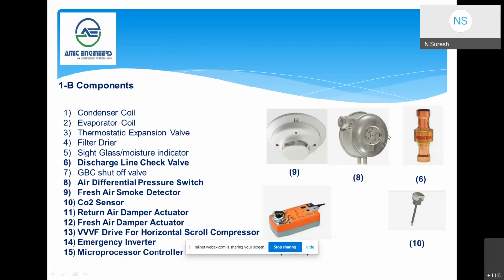So earlier there was no pressure switch, so the filter would get clogged and we would be running the compressor for more time. To avoid this, this differential pressure switch is introduced in the system. And there is a safety device, the fire smoke detector, a fresh air smoke detector. This is the smoke detector which is provided in the path of the fresh air.